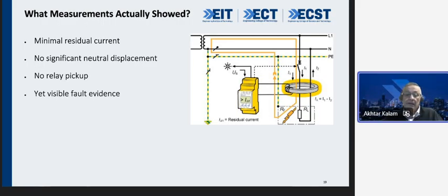Now, let me tell you what the measurements actually showed. It showed very little residual current, no neutral displacement. The relay did not pick up and there was fault evidence. This is actually the case. The fault is there, the relay did not pick up.